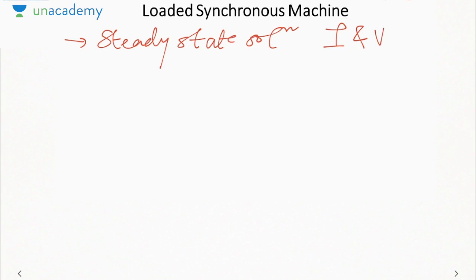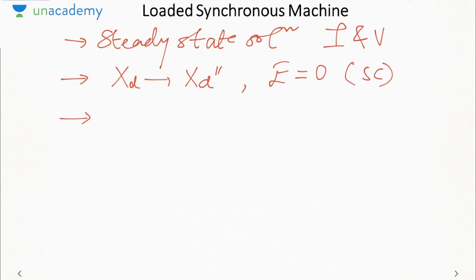The other method to deal with a loaded synchronous machine is to first obtain a steady state solution, that is the solution of the system before the occurrence of the fault. In the steady state solution, what you will compute is all the currents and voltages at any point of interest. Then, in the next step, you will have to replace all the reactances by their subtransient values, and we have to make all the EMF sources 0, that is, short circuiting. Now what we will get is a passive Thevenin network. Why passive? Because there is no energy source, so there is no active network. Now we will excite this network by the negative of the pre-fault voltage in series with the fault impedance ZF.